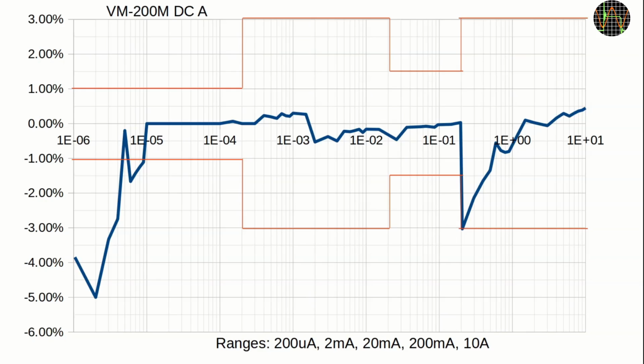And similar, the DC amps. Here the VM-200M has a slightly strange specification, varying between 1, 3, 1.5 and back to 3%, but has no problem meeting it. Accuracy and resolution for currents greater than 200 mA is reduced in that the next higher range is already 10 amps. Apart from this, I have no complaints, and especially from 10 to 200 microamp, the meter was again extremely accurate.